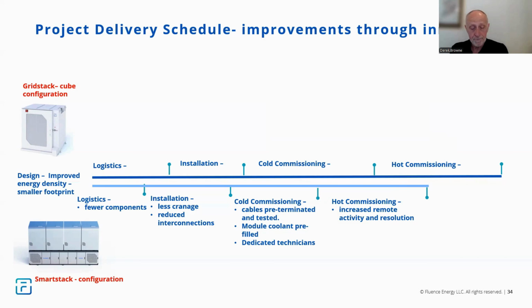And then from a logistics perspective, overall, we have fewer components on the smart stack because, as Lucy mentioned, the string inverters and the coolant systems are all built into the bottom skid itself. So we've fewer pieces to move around site and to deliver. And because we've less cranage and reduced interconnections within the system itself, we can make the installation work in a lot more efficient sort of way. The logistics side and the installation side is combined, if you like. We have a just-in-time delivery arrangement, and it avoids the double handling of all the equipment.